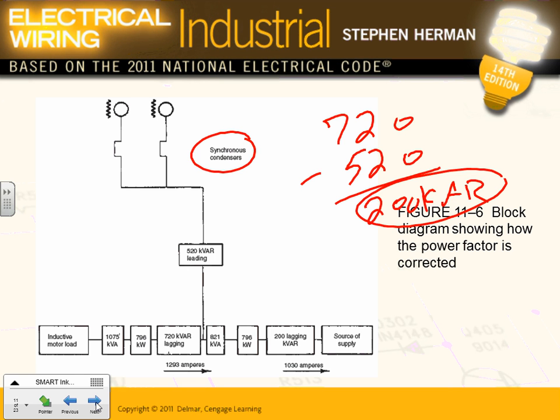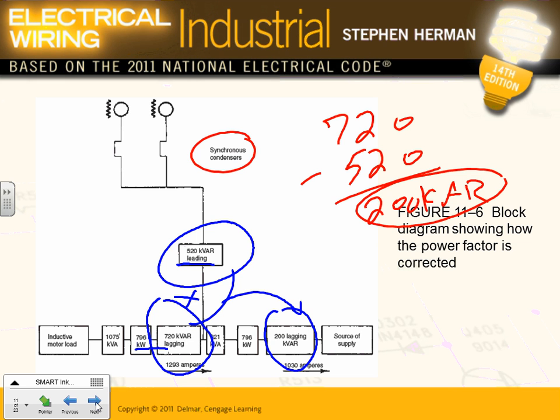I want you guys to look at this because if you don't see that one, it's really hard to understand it. Here's how much I introduce, 520. Here's how much I have in my system, lagging power factor. These are leading. Can you guys see the leading and the lagging here? When you added them together, they're in opposite directions, so actually you're subtracting them, and they reduced down to this value. So it's actually using the 520 kVAR to run them? What they do is they offset each other. Because something's got to make them spin, right? Make what spin? Make them operate? Yeah. Synchronous. Yeah.